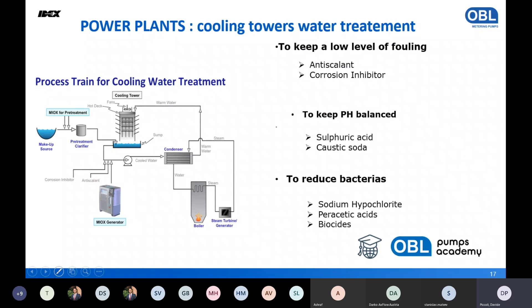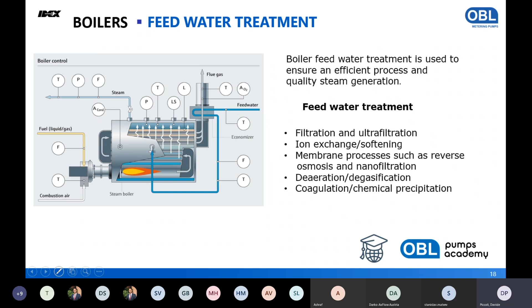In every plant, again, in the plant you saw before, there are also big boilers. Boilers need to warm the water for the process, many times using the flue gas, and the water that is injected into the boilers again needs to be treated. The main important processes here are filtration and ultrafiltration, because we need to avoid the entrance of any kind of particles into the boiler with mechanical filtration. There is ion exchange, and there is again reverse osmosis with deaeration, degasification. After that, all the chemicals that remain in the water need to be removed with coagulation and chemical precipitation.